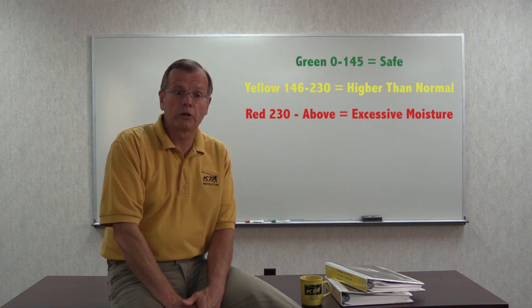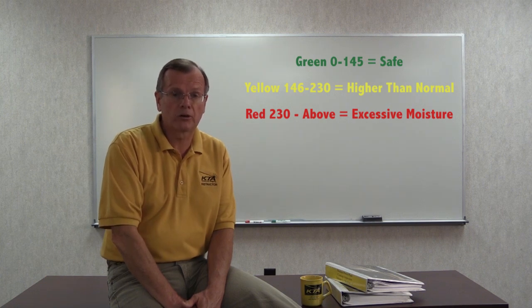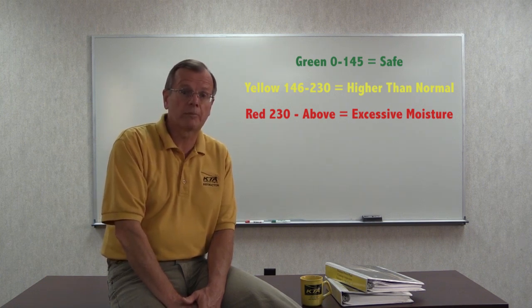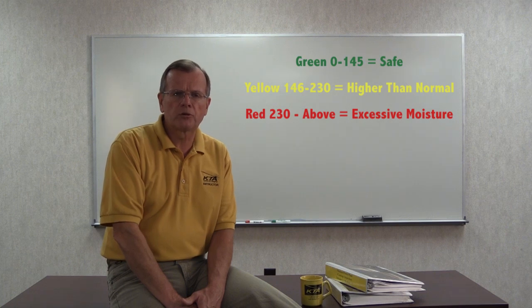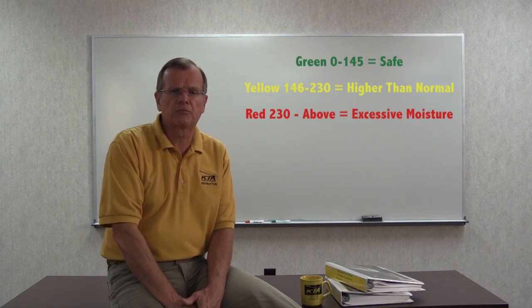Green or good is usually 0 to 145 units which is safe air dry conditions. Yellow is between 146 and 230 units signifying moisture levels are higher than normal but not critical. Further investigation is recommended. And red is greater than 230 units representing excessive moisture levels.